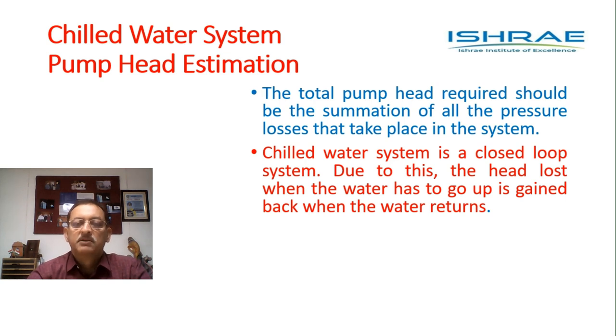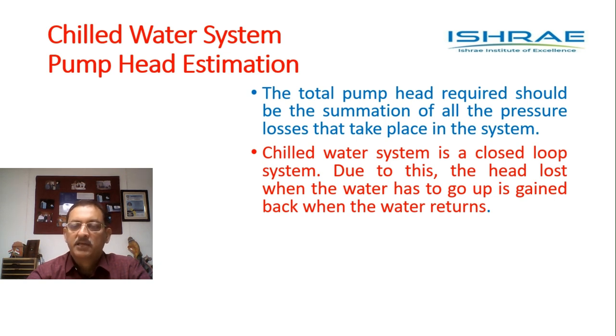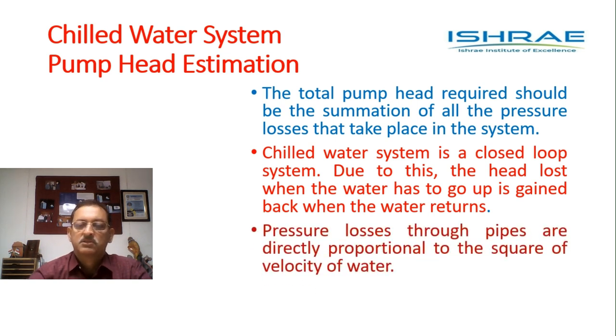We should remember that unlike a fresh water system or a fire main system, a chilled water system is a closed loop system. In the other two examples, the water gets consumed — it is only one way. But in a chilled water system, the water does not get consumed. Whatever water goes up has to come back, and when water is going up pressure is lost, and when water comes back that pressure is gained again.